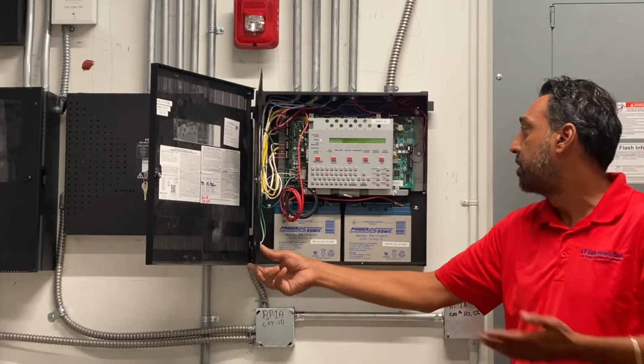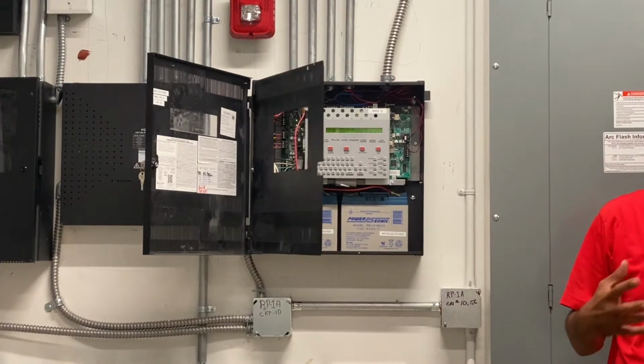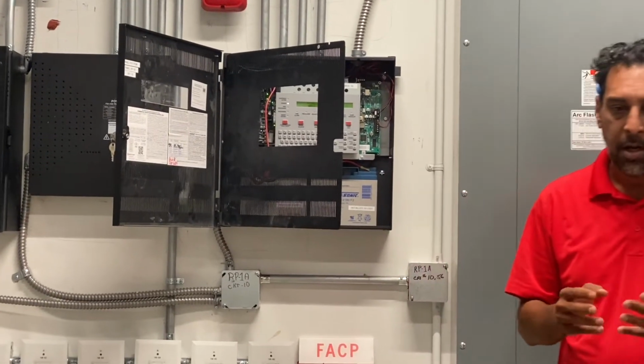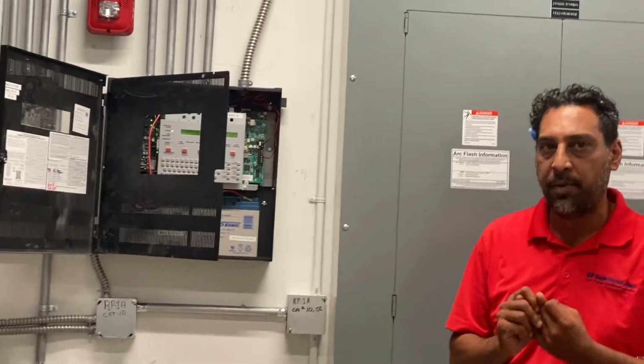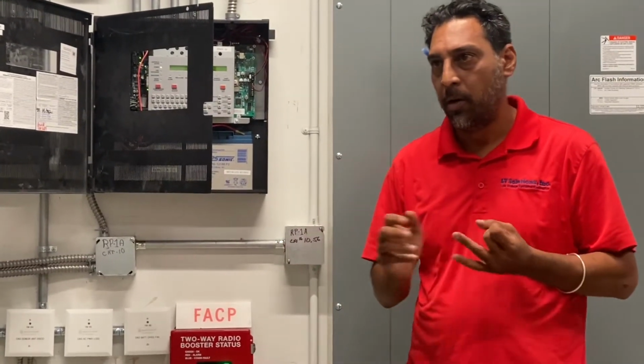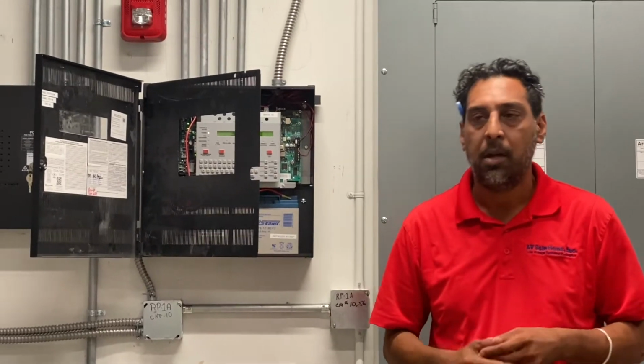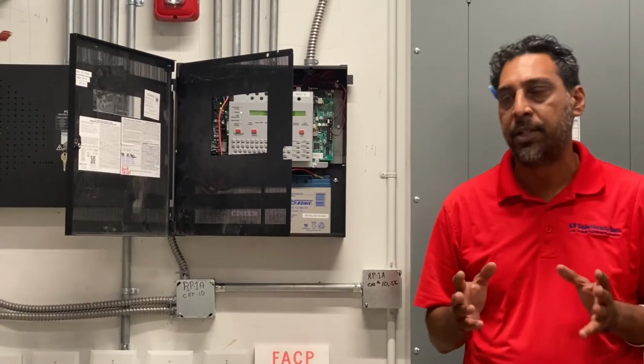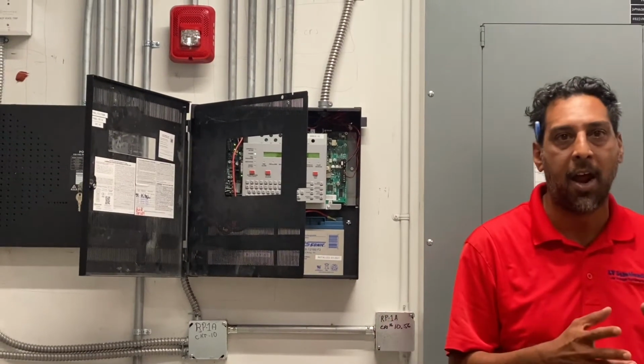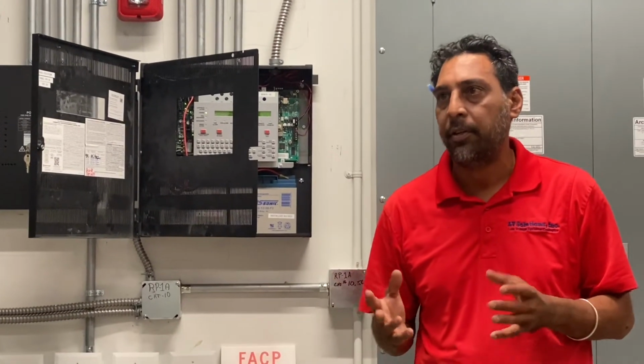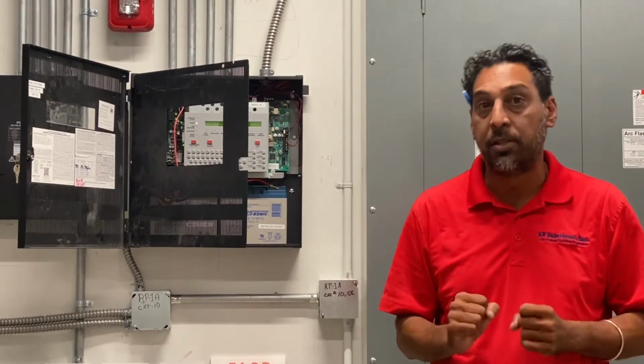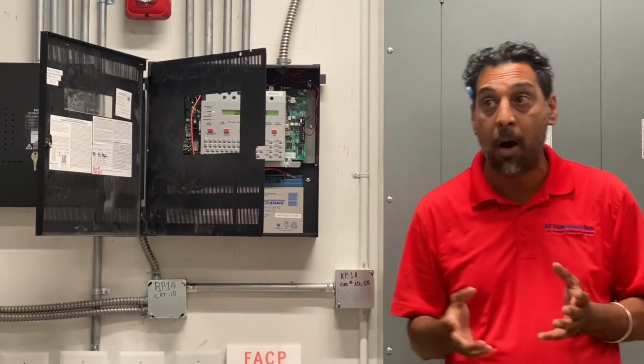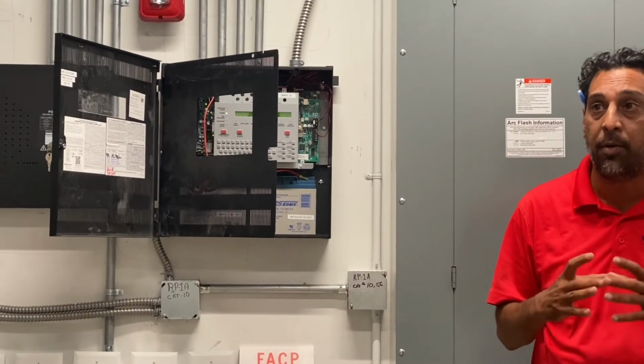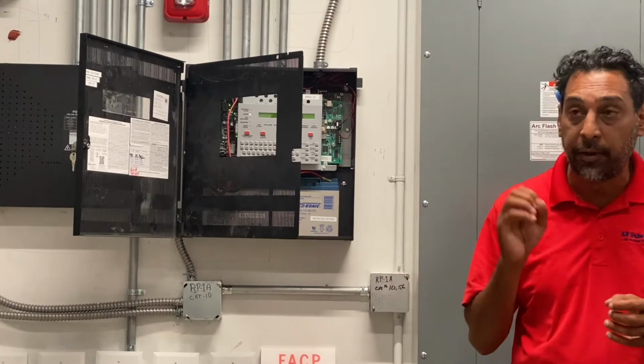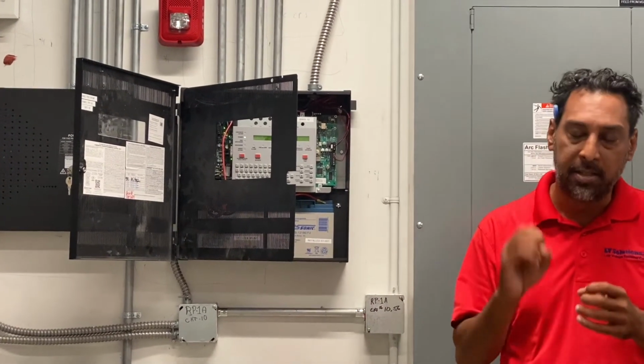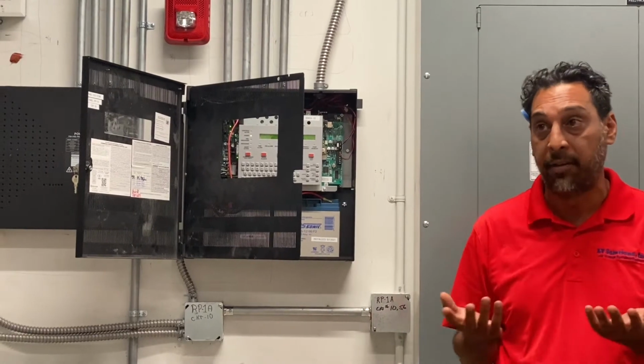On your supervisories, as you see there, it just went back to normal. We have two types of supervisories, what we call non-latching or track supervisory, or latching. Your latching supervisories we have here are smoke detectors, or what we call duct detectors, on your air handler units. If any of those go off, it's going to shut that unit down, which is why we have it latching. These are what we call photoelectric detectors. It looks for particles passing through a light. When it sees too many particles passing through a light, it activates the detector.